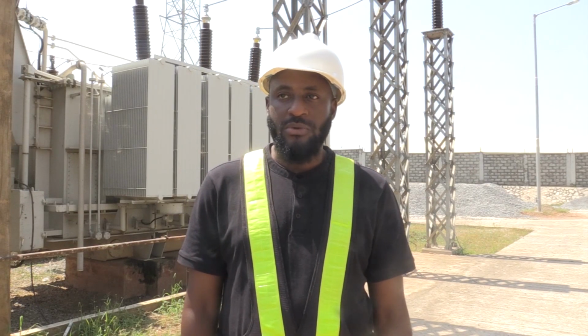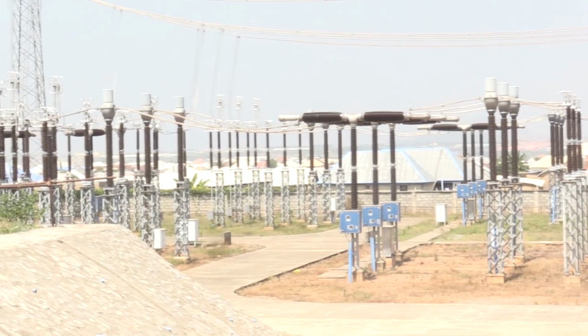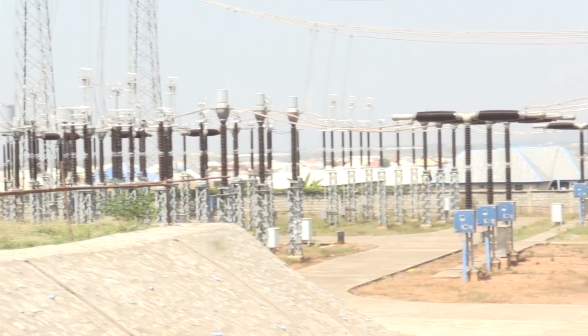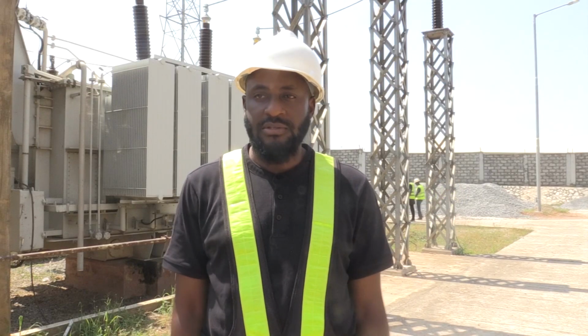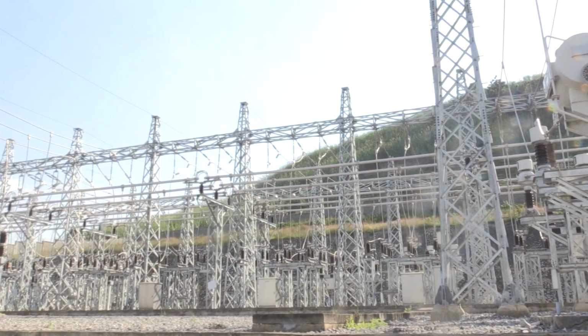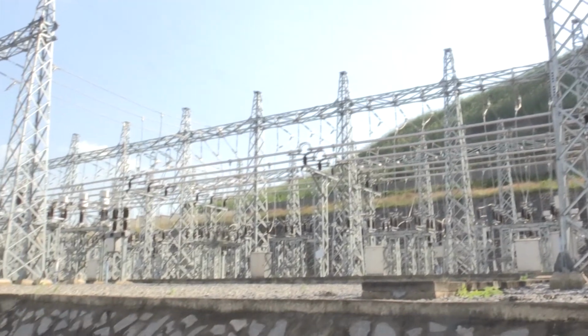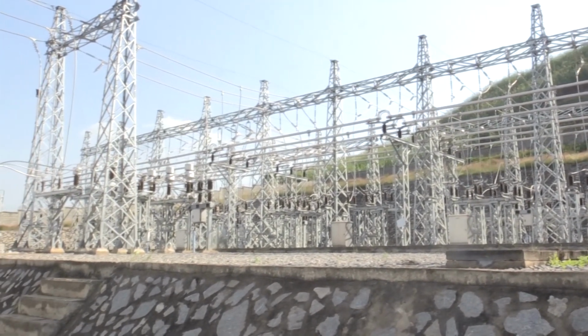Speaking at the West Main Lugbe project site, Engineer Yusuf Munir, a project engineer at the TCN AFD Project Implementation Unit, said: 'This is lot 4, West Main Lugbe. It's a 2 by 150 MVA substation, and we have 3 60 MVAs as well, making it a 330 by 132 by 33 kV substation. It's a hybrid substation, a mixture of AIS and GIS.' The Lugbe substation has a significant capacity, reaching up to 300 megawatts of power evacuation, covering Lugbe and catering to the needs of the Edu industrial estate.